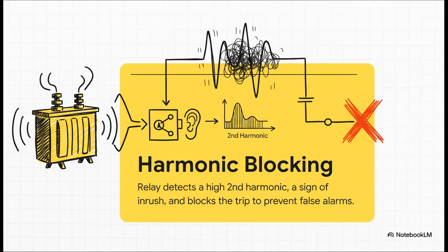A real fault has a very clean sound, a pure tone, right at the normal power frequency. But that magnetizing inrush has a really distinct, distorted sound. That distortion is made of other frequencies, which we call harmonics. And it turns out inrush current is packed with a specific one, the second harmonic. So the relay is basically programmed to listen for that specific distortion. If it hears that second harmonic, it says, that's just inrush, no big deal, and it blocks itself from tripping.